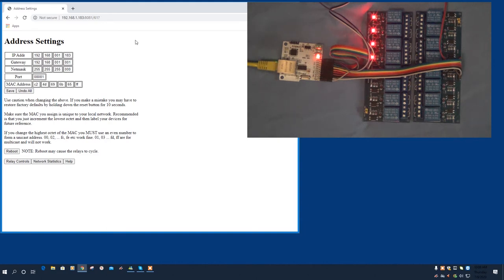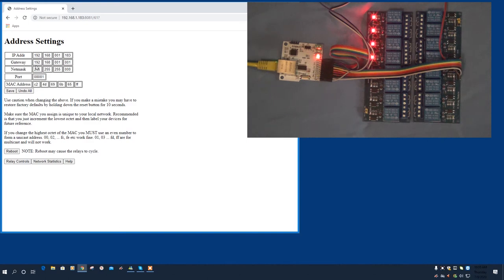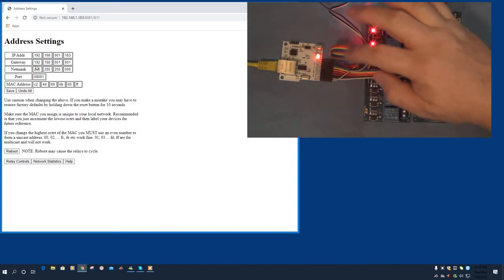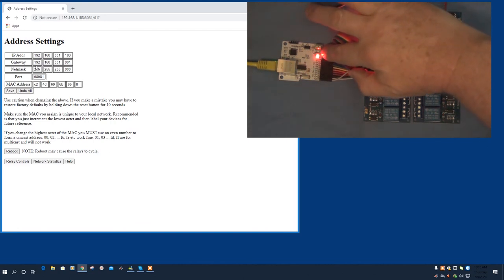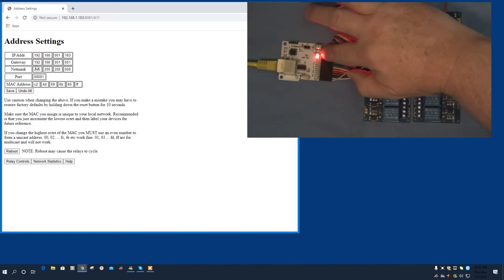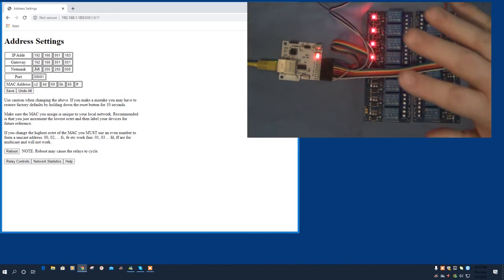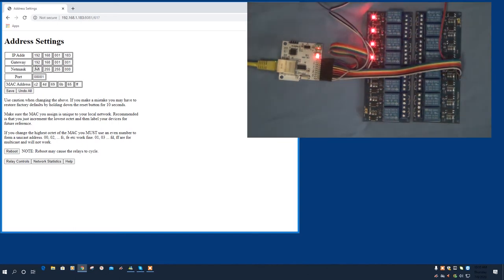By the way, if you make a mistake in any of this stuff and can no longer contact the network module, all you have to do is press the reset button. I'll point to it here. It's right next to the LED. Hold it down for about ten seconds and you'll see the LED go out. When you release the button, the module will return to its default settings.